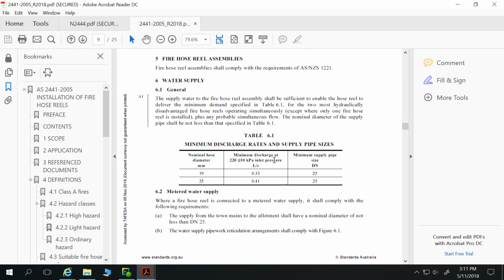Well, the supply of water to a fire hose reel assembly shall be sufficient to enable the hose reel to deliver the minimum demand specified in table 6.1 for the 2 most hydraulically disadvantaged fire hose reels operating simultaneously. That was that, yeah. So basically what this is telling us is the only stipulation here is that you have to have enough water or enough pressure to that fire hose reel. So it can be from a metered water supply. So it can be from a mains water supply. It just has to meet this. So 0.33 litres per second for a 19 mil and 0.41 litres per second for a 25 mil.